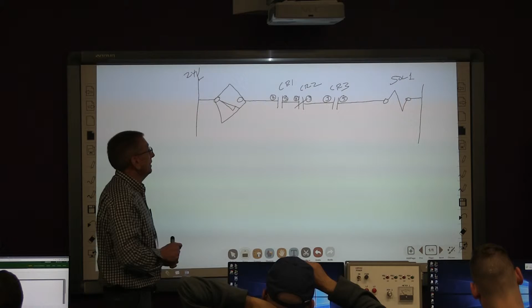CR3 is pulled in, so you can pretty much assume that contact is closed. What state does CR2 have to be? It has to be de-energized. What about the relay coil itself? De-energized - so you look at CR2 and make sure it's de-energized. You look at CR1, it's energized. So right there, you haven't even picked up a meter yet.